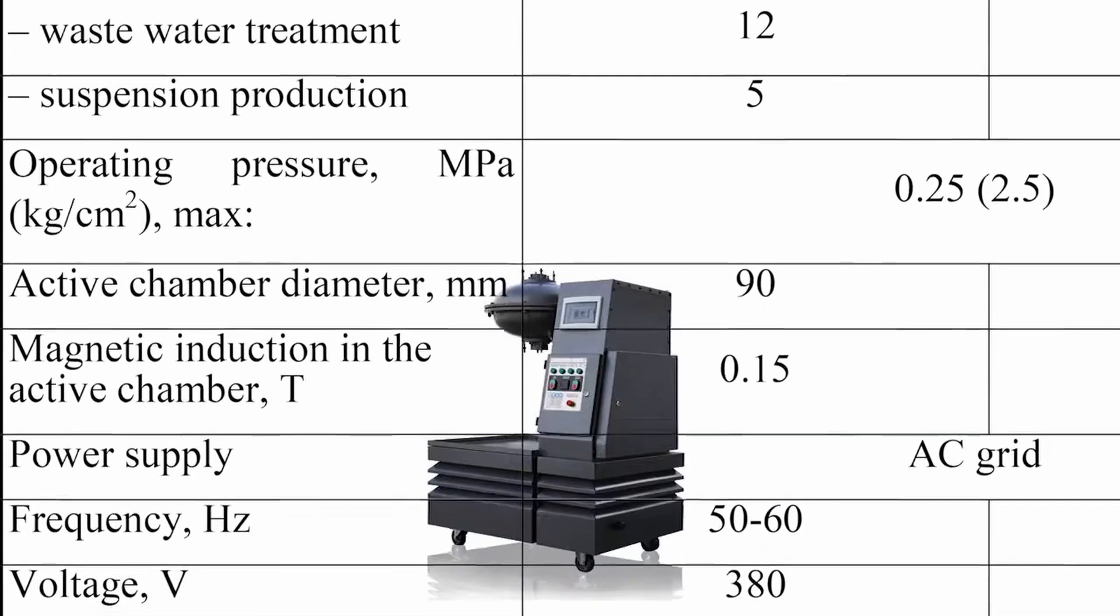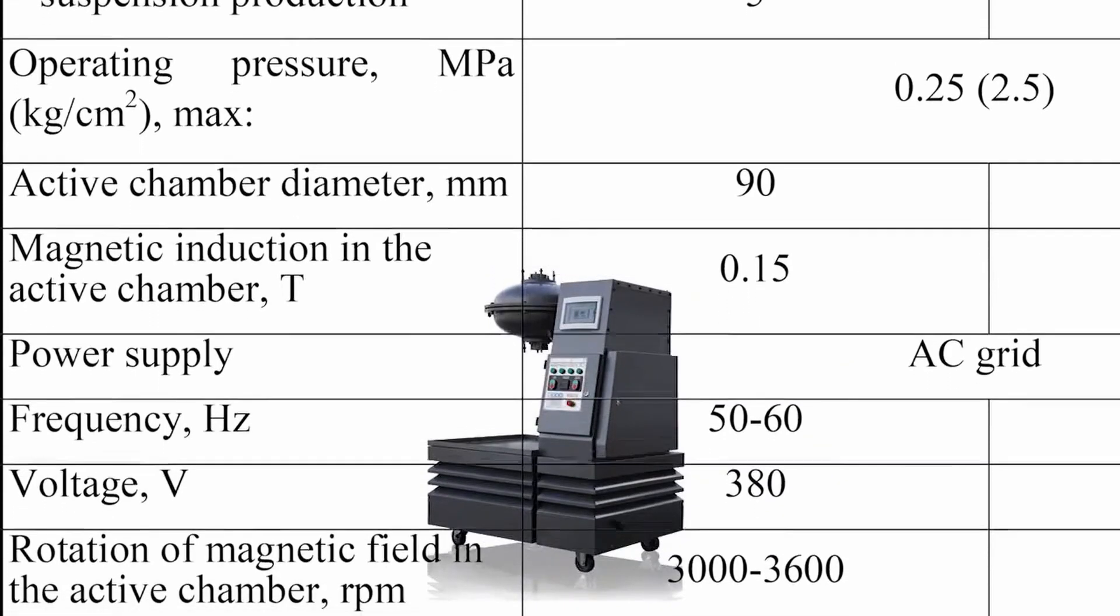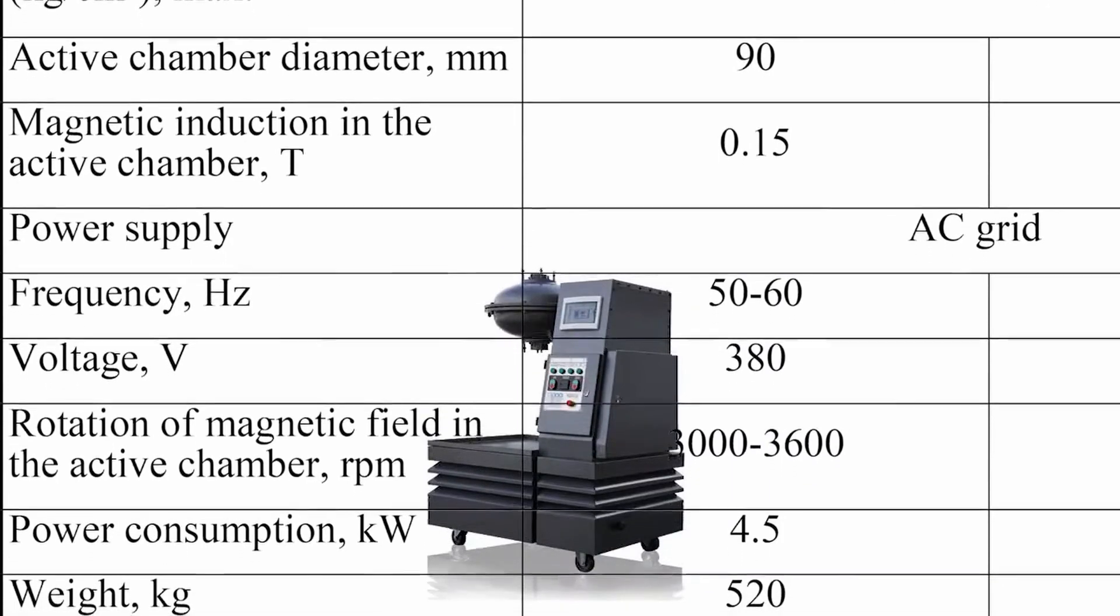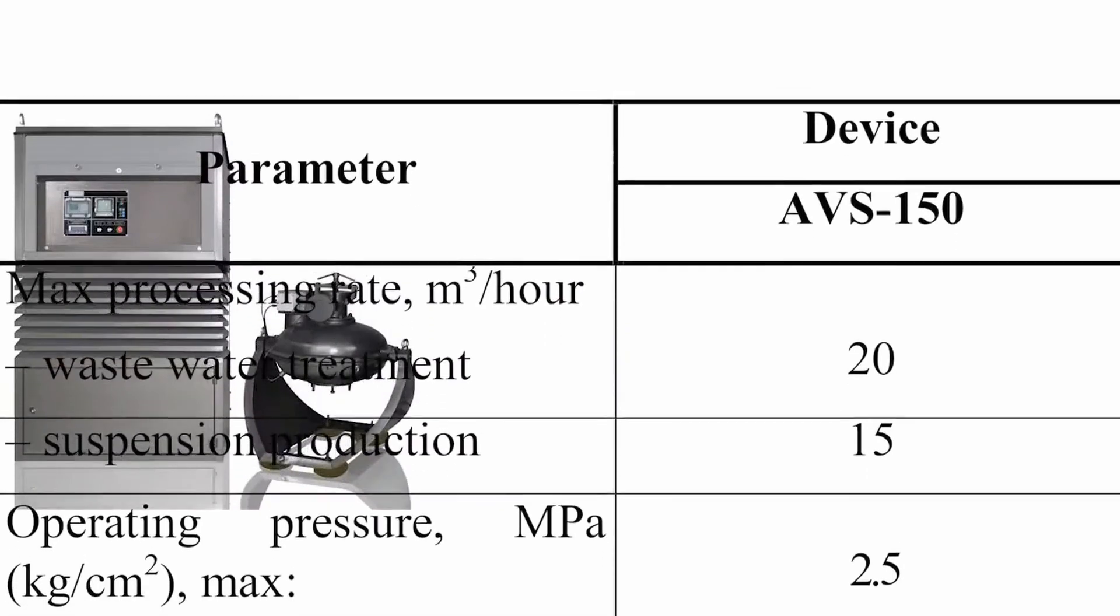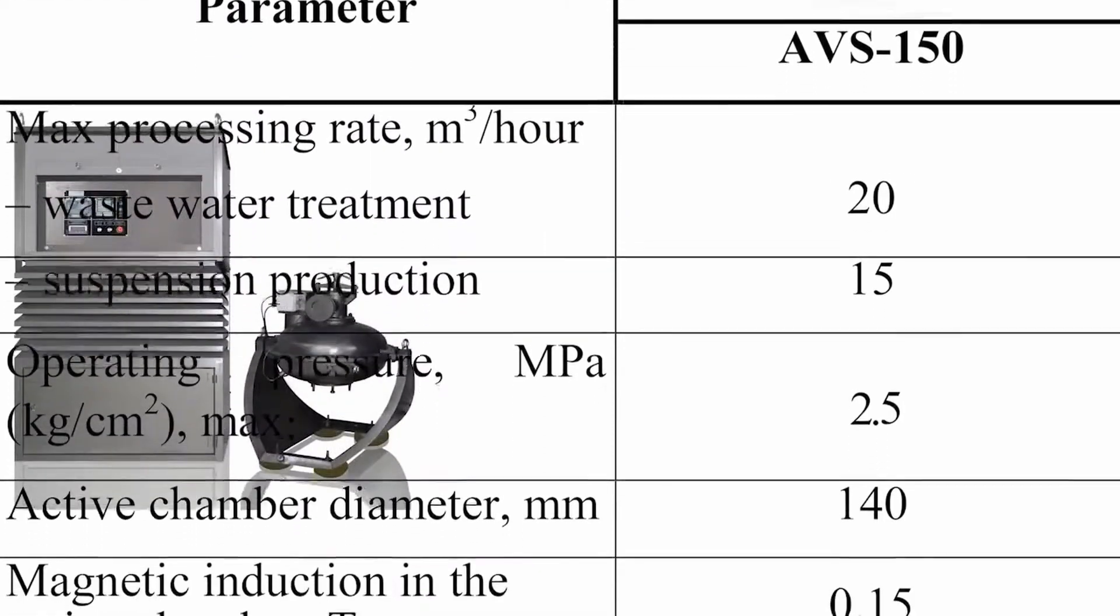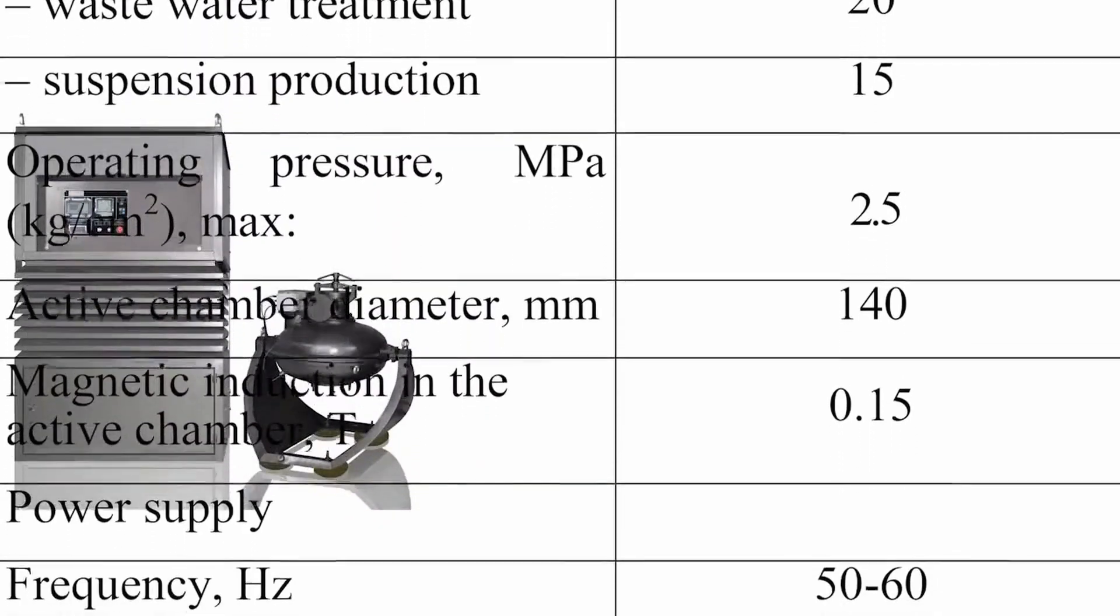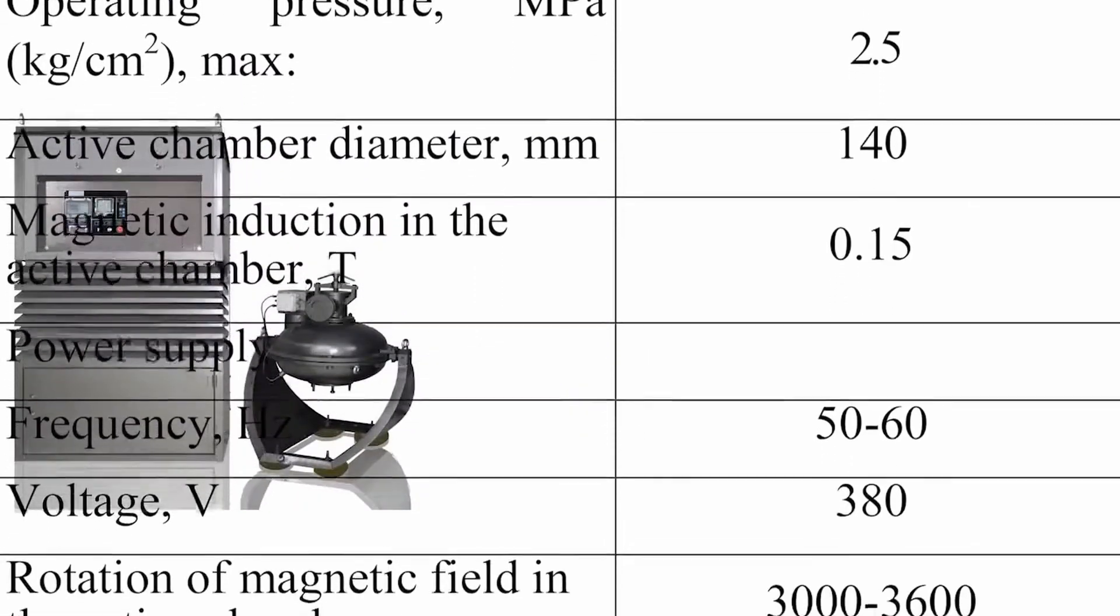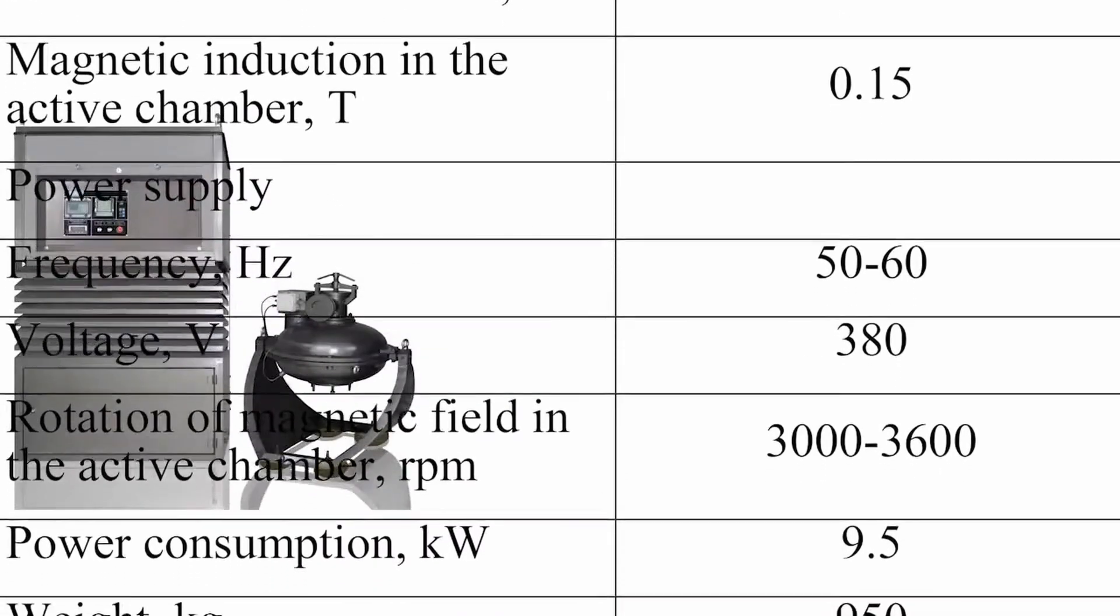For AVS-150 device: the maximum capacity during wastewater treatment is 20 cubic meters per hour; when obtaining the suspension, it equals 15 cubic meters per hour; maximum operating pressure, 2.5 megapascal; rotation speed of magnetic field, 3000 revolutions per minute; power consumption, 9.5 kilowatts.